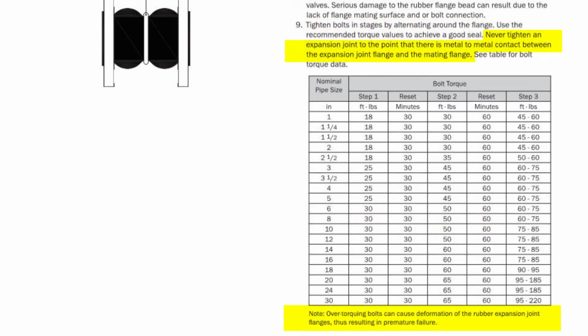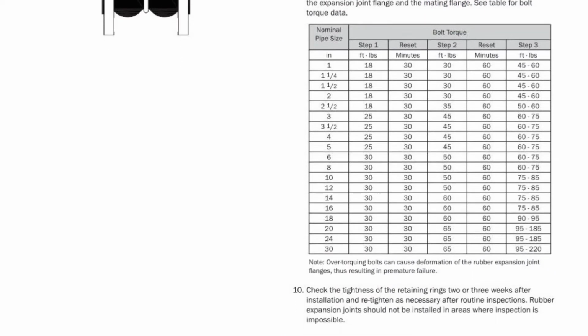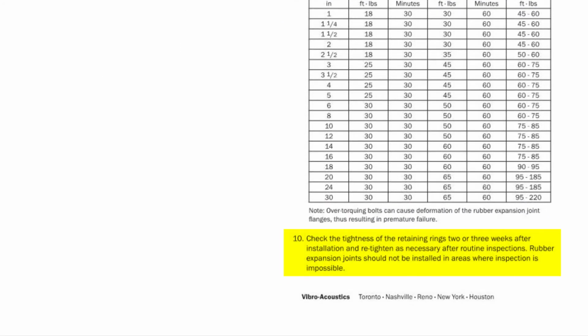Note that the bolts should never be tightened to the point where the expansion joint flange and the pipe flange touch each other. There is a cautionary note below the table that warns of premature failure if the bolts are over-torqued. The flange bolts should be checked periodically to ensure they remain in the torque range, so regardless of when the site inspection occurs, the flange bolts should always be in that range.